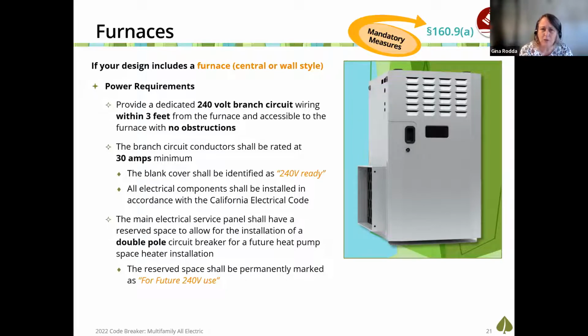I've got a lot of questions on, is this the conduit? No, this is the actual wiring, and 208 volt is not what they're asking for. They're asking for 240 volt. It also has to be a 30 amp service to that branch circuit. The conductor needs to be 30 amp.